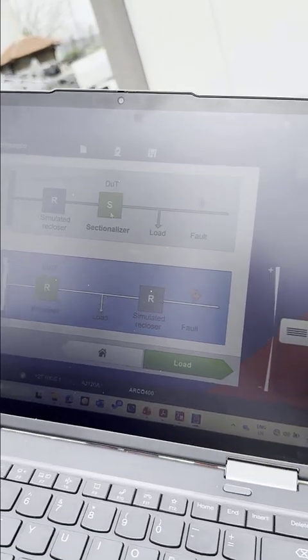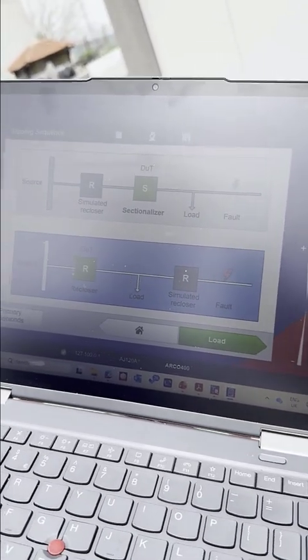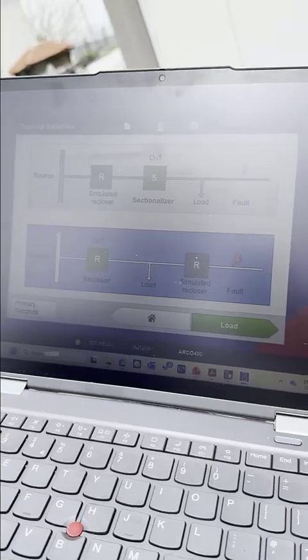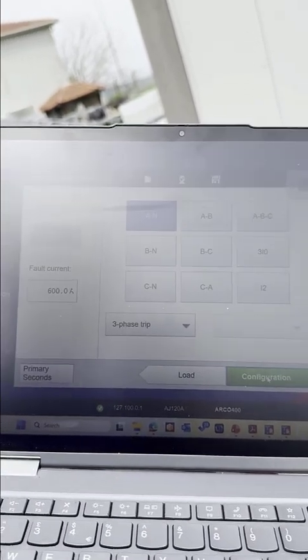The ARCO 400 will simulate upstream recloser, because there is no circuit breaker in the sectionalizer. It's only a disconnector or a switch, no any arc quenching medium. And if you select the device under test here to be recloser, it will be simulated with the downstream recloser. Then you can go for the load. Here is a pre-fault to be more than or longer than the reset time or the reclaim time of the circuit breaker. So we have 10 seconds, now 11 seconds is more than enough. Then you can go for the fault.